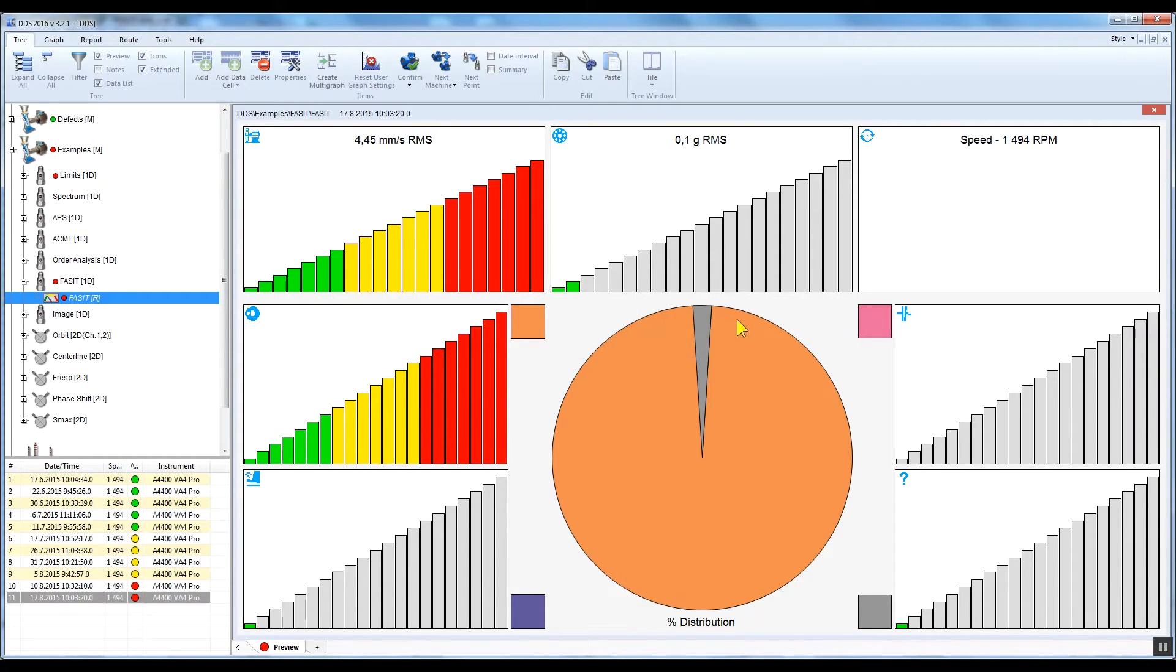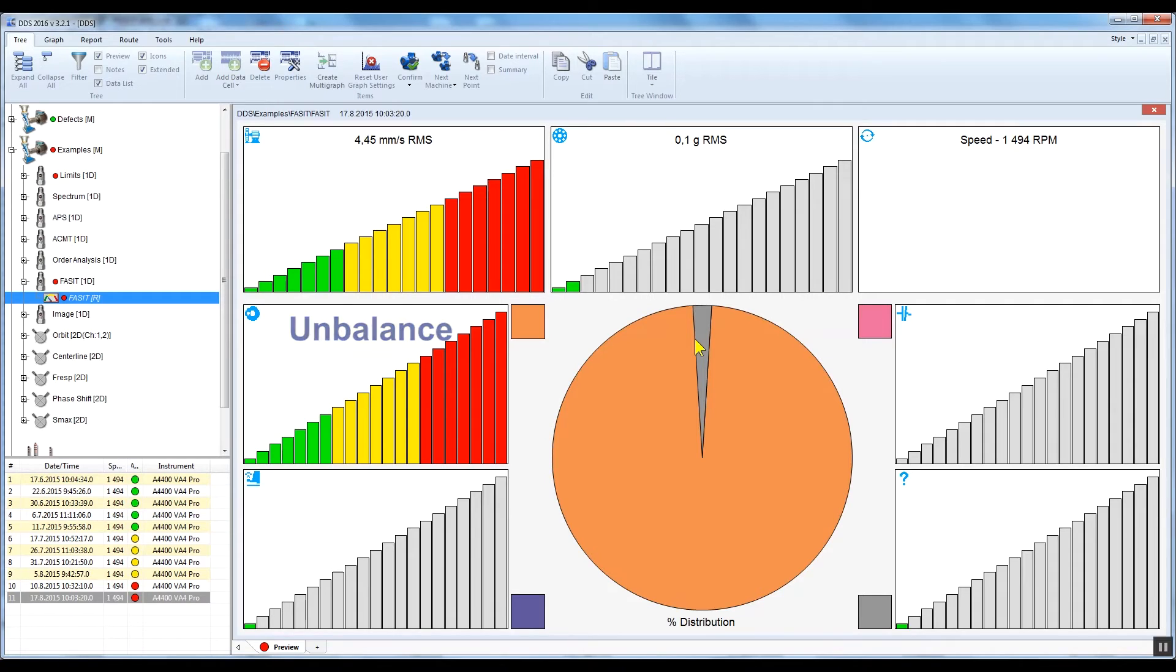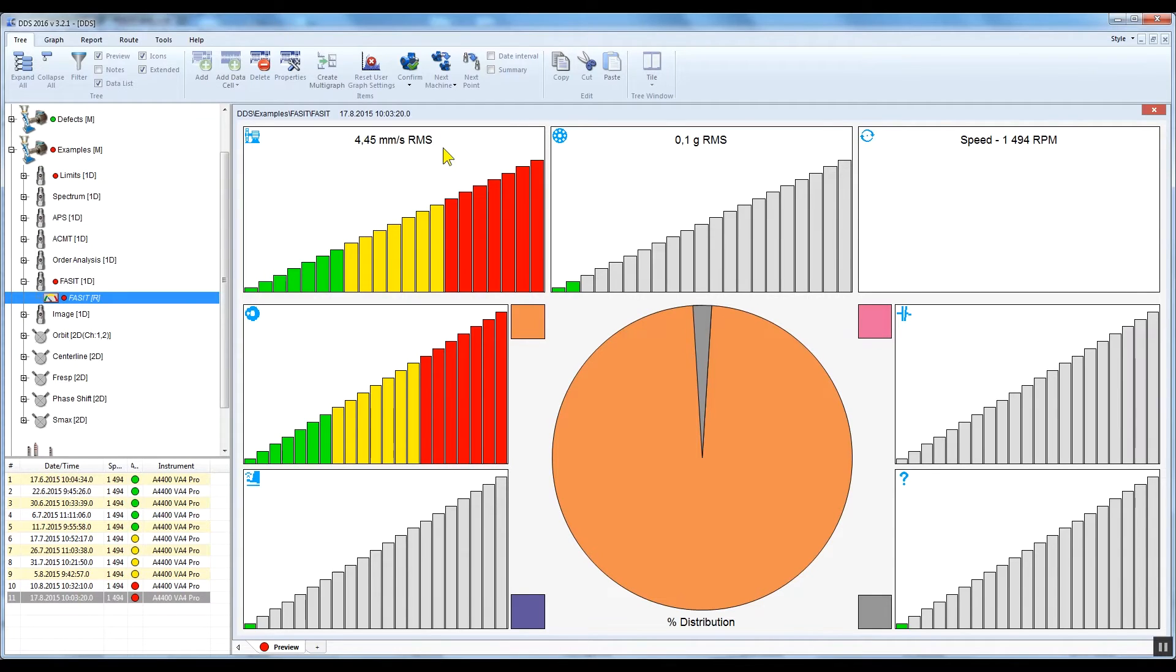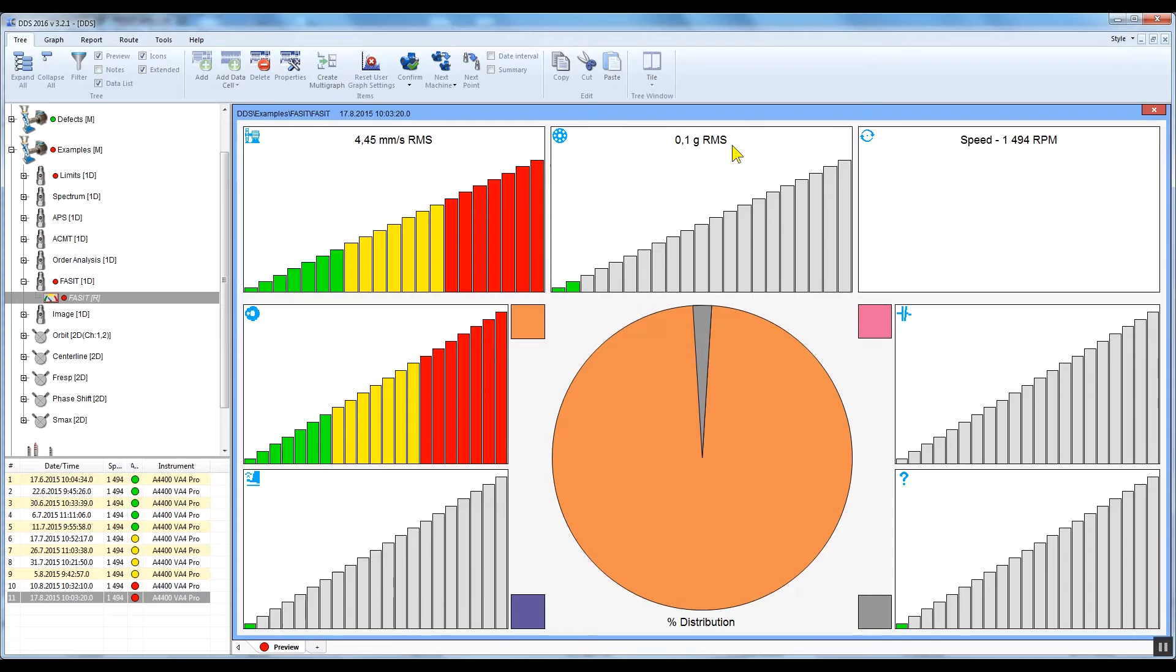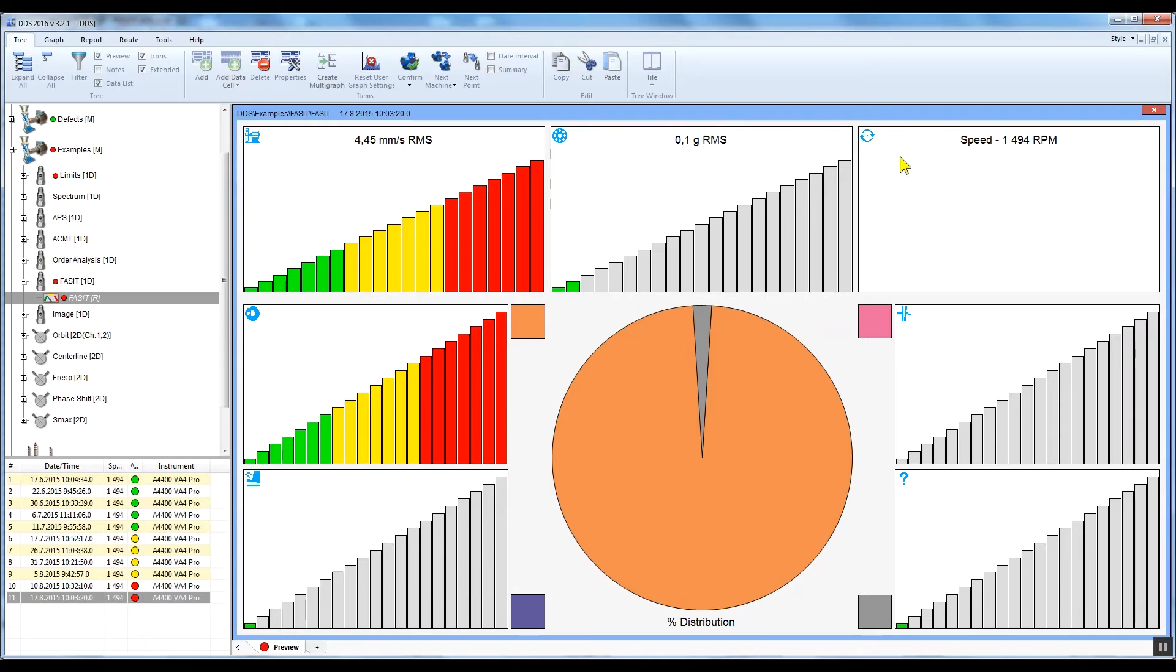In the top left corner of the graph window you can see vibration velocity in the 10 to 1000 Hertz range in millimeters per second RMS. This indicates the overall machine condition. Next to it there is acceleration in the 500 to 16 kilohertz range in G RMS, indicating bearing status. In case you have a licensed version of DDS, the range is 500 Hertz to 25 kilohertz. And in the top right corner you can see the speed.